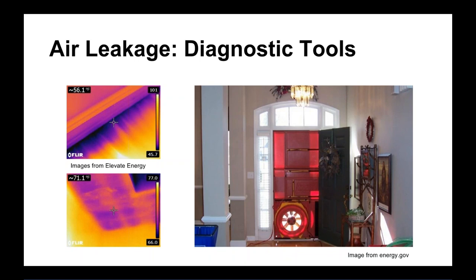This blower door is essentially a cover on the door with a hole for a large fan. It depressurizes the house by blowing air out of it, creating a slight vacuum indoors. We usually try to depressurize the home to negative 50 pascals and then figure out what volume of air is moving through the house. Qualitatively, once you have the home depressurized, you can walk around and feel air moving in through the leaks. Quantitatively, you're measuring the air volume out through the fan at a specific depressurization in cubic feet per minute, which you can represent as air changes per hour.